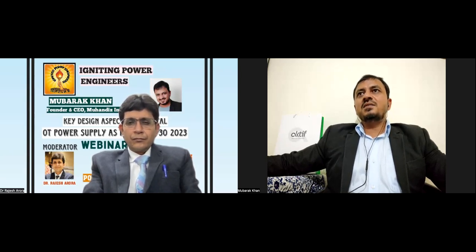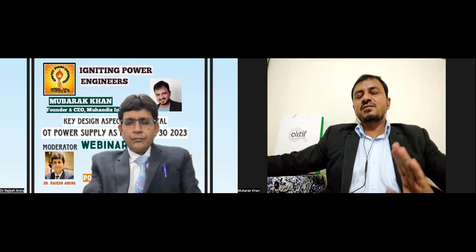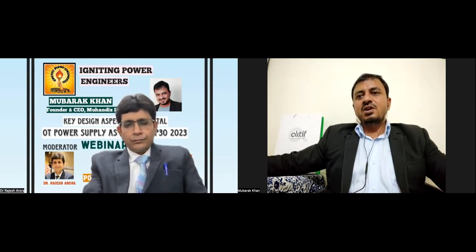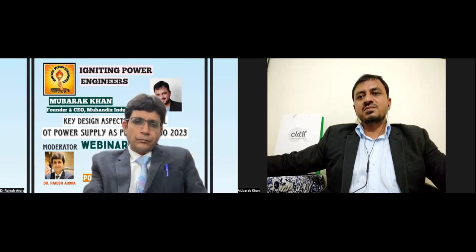So that is why, if there is an alarm, we should take action directly and try to solve it rather than keeping it there because the system is not tripping. Some people may ignore it, leave it there and keep the operation on. But we should not do that. We should have an insulation monitoring and fault location system, detect the fault and eliminate it as soon as possible. Keep the system healthy.